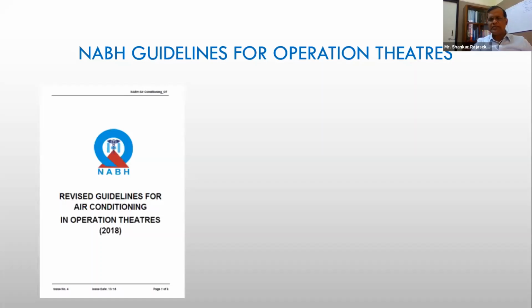But it covers just the operation theaters. There is no mention about anything else, nor do they talk about the air handling units or the ducting or anything with reference to the operation theaters. They talk more about the indoor conditions that are required and the equipment that we will have to use, not so much about the specification or the details of the equipment.